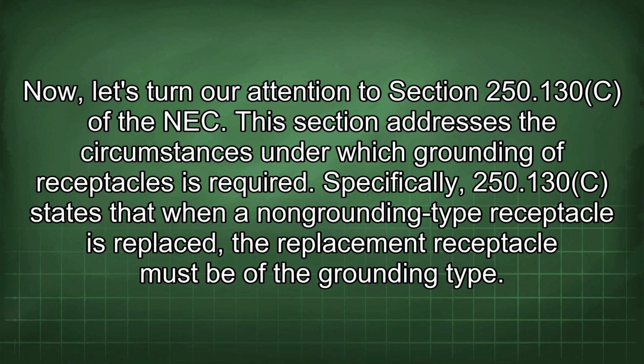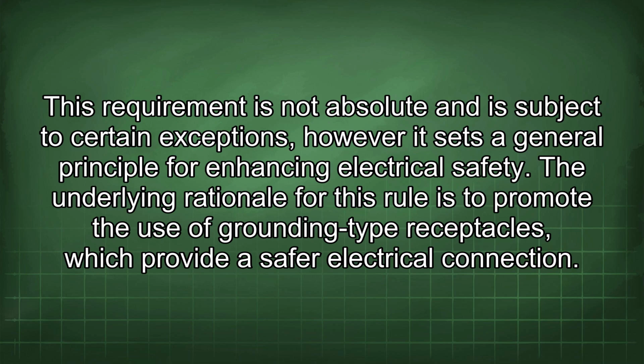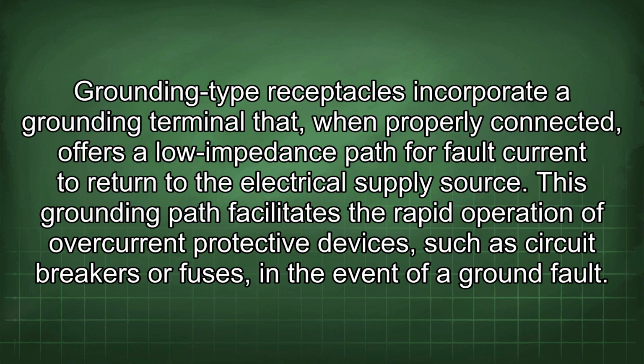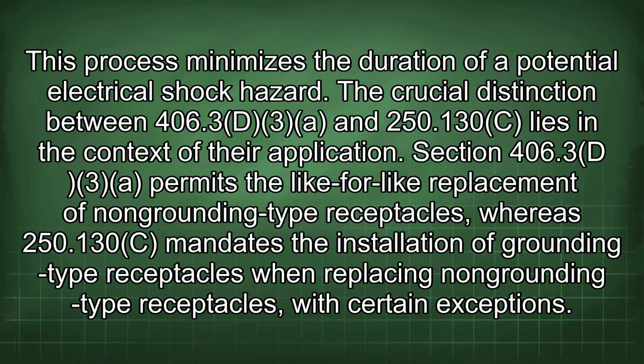Now let's turn our attention to Section 250.130c of the NEC. This section addresses the circumstances under which grounding of receptacles is required. Specifically, 250.130c states that when a non-grounding type receptacle is replaced, the replacement receptacle must be of the grounding type. This requirement is not absolute and is subject to certain exceptions, however, it sets a general principle for enhancing electrical safety. The underlying rationale for this rule is to promote the use of grounding type receptacles, which provide a safer electrical connection. Grounding type receptacles incorporate a grounding terminal that, when properly connected, offers a low impedance path for fault current to return to the electrical supply source. This grounding path facilitates the rapid operation of overcurrent protective devices, such as circuit breakers or fuses, in the event of a ground fault. This process minimizes the duration of a potential electrical shock hazard.